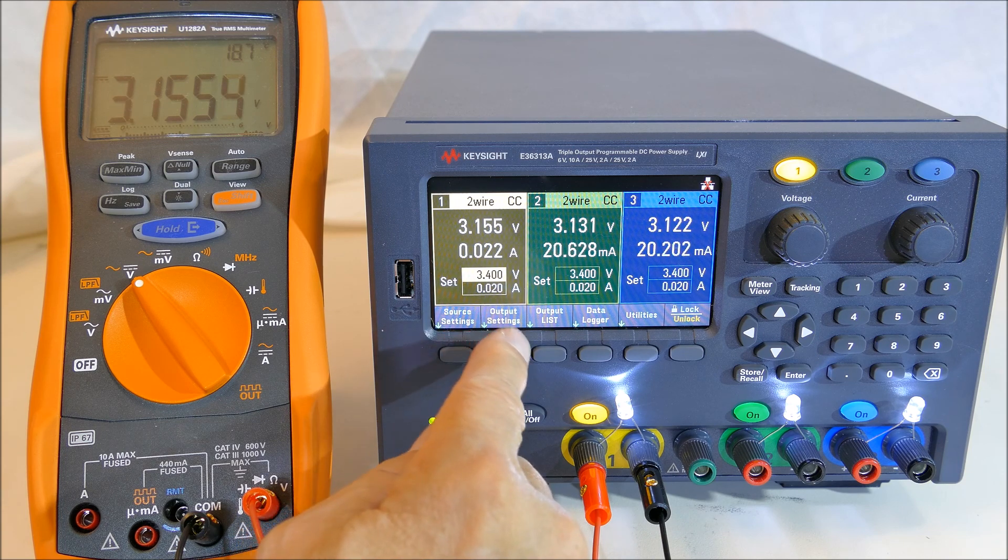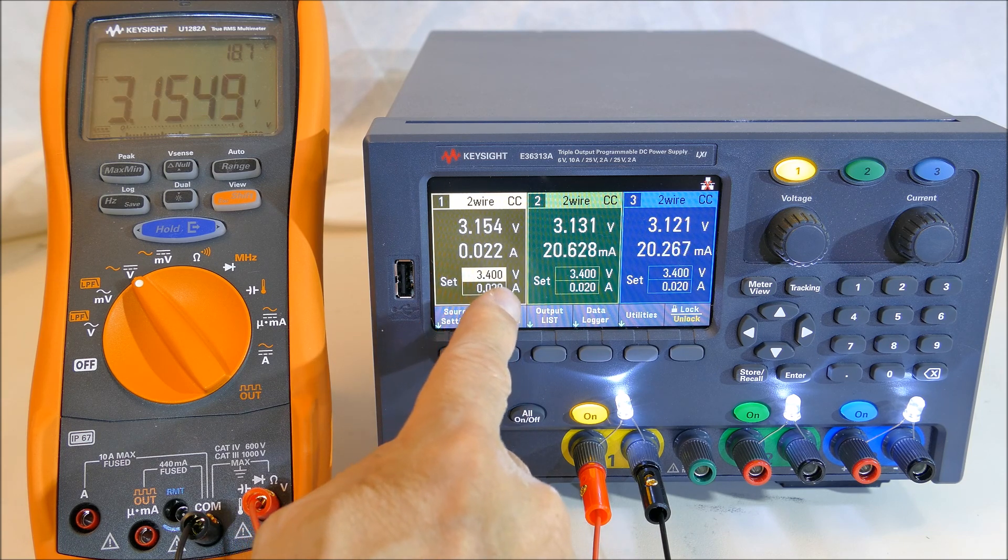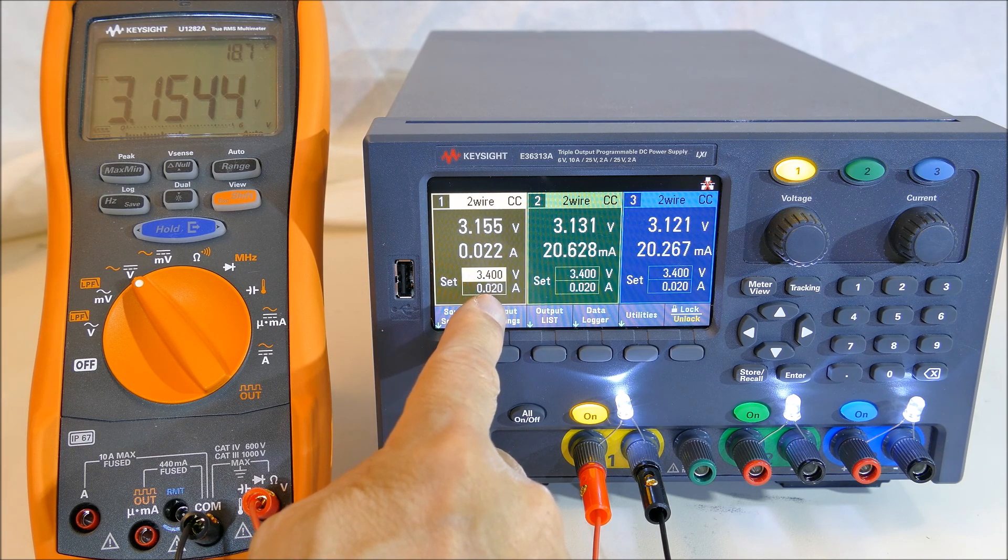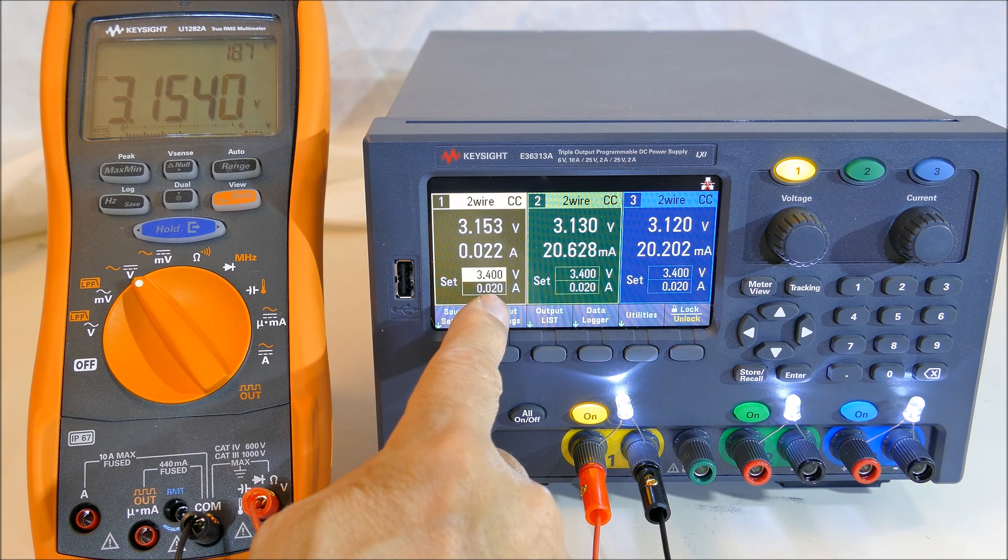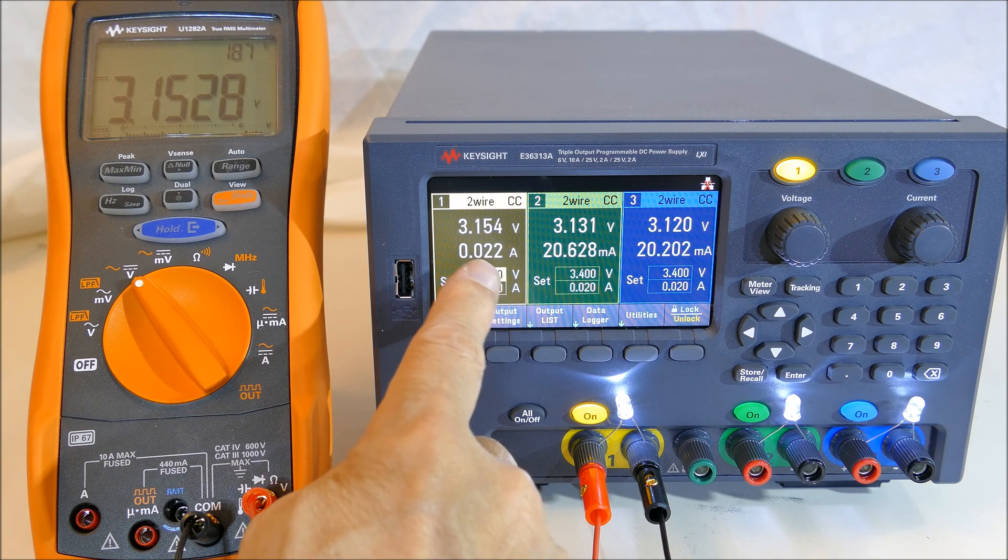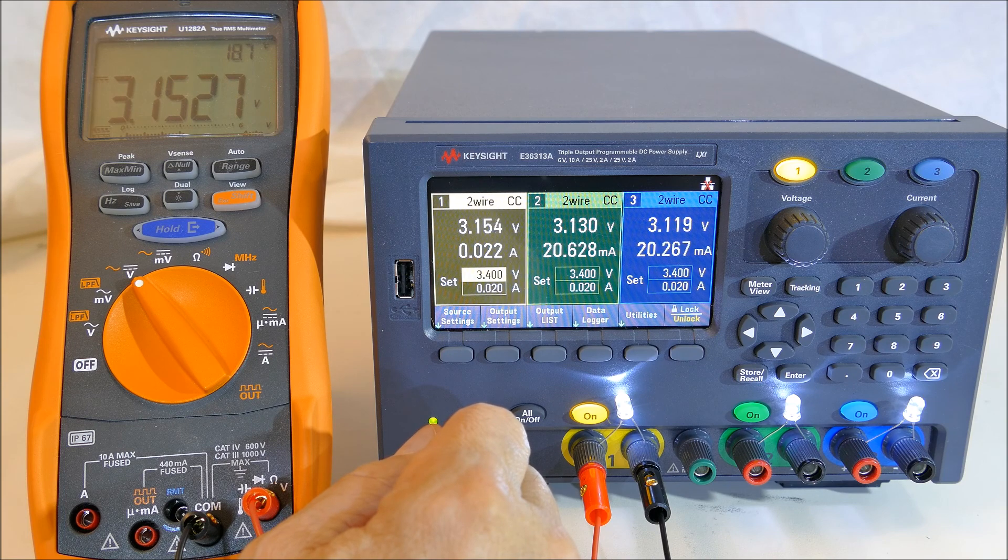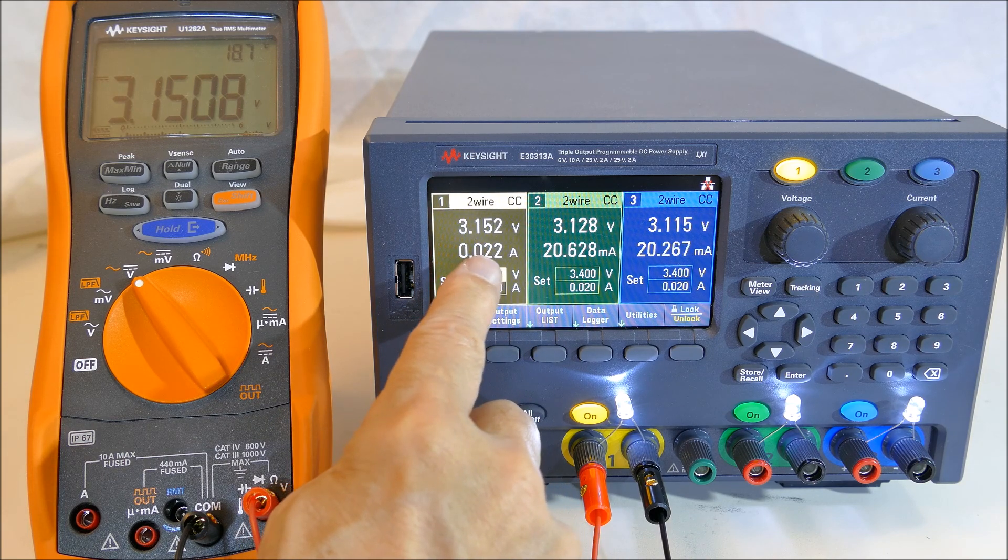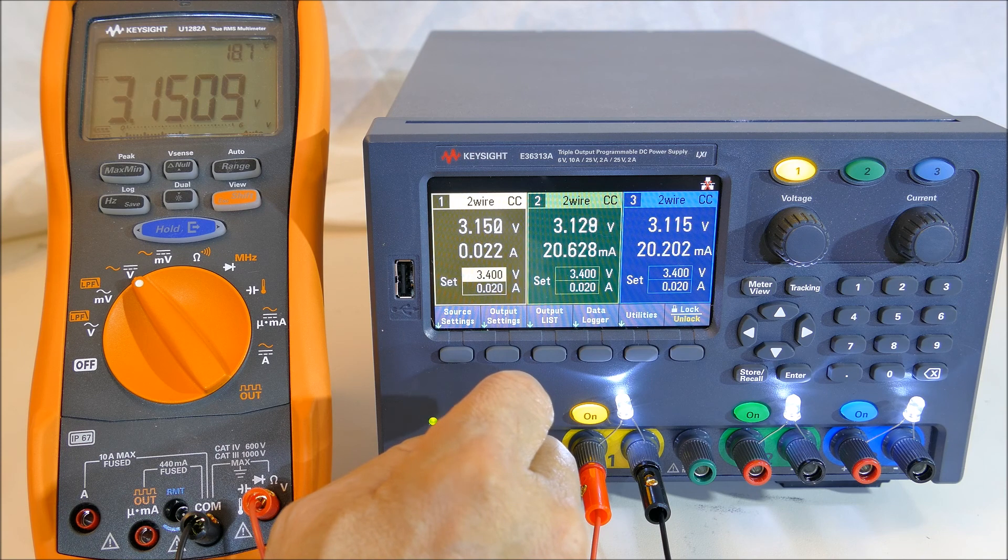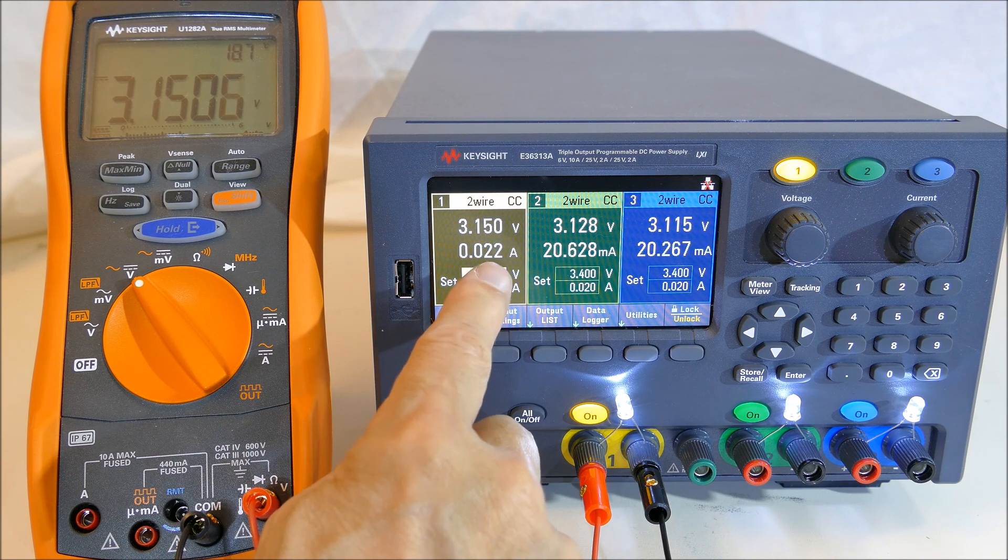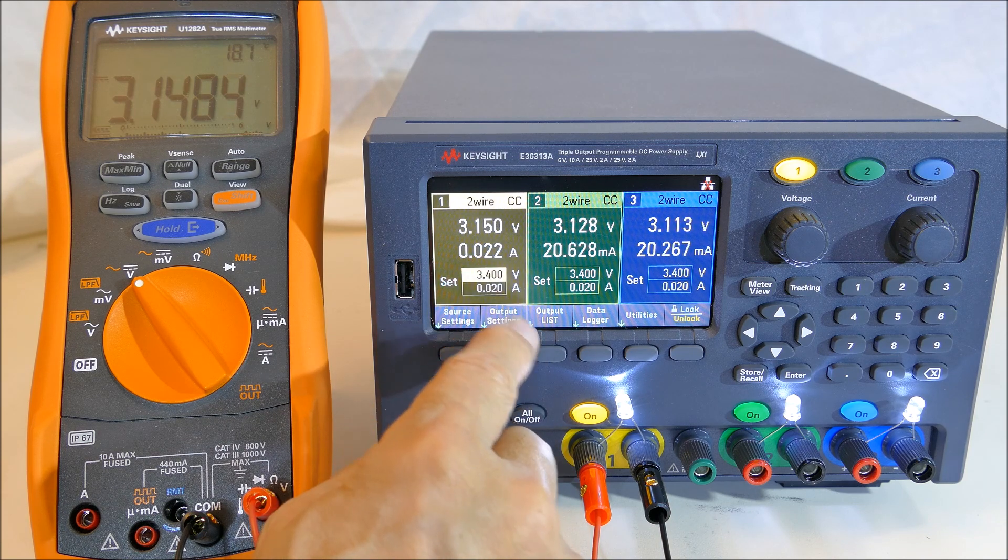If you really wanted to get more accurate, you could simply adjust this set point here to say 18 milliamps and this would come back to 20. You can use this current meter to tell you exactly how much current is coming out. Even though you set it to 20 milliamps, this number is actually more accurate.